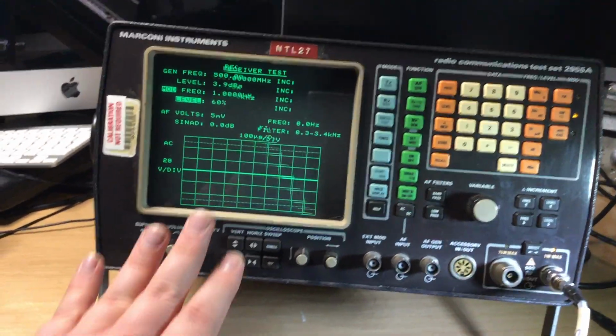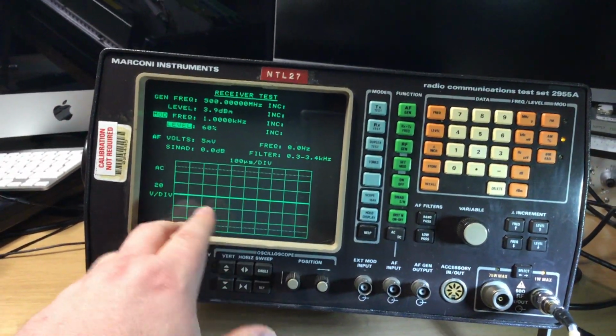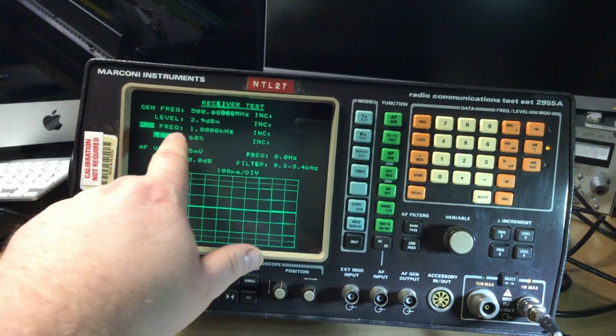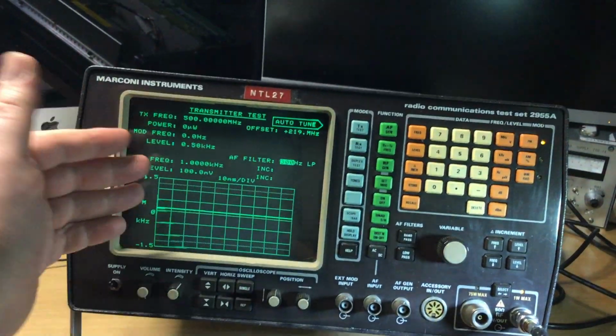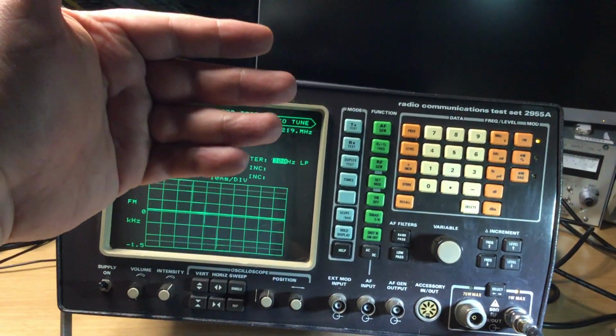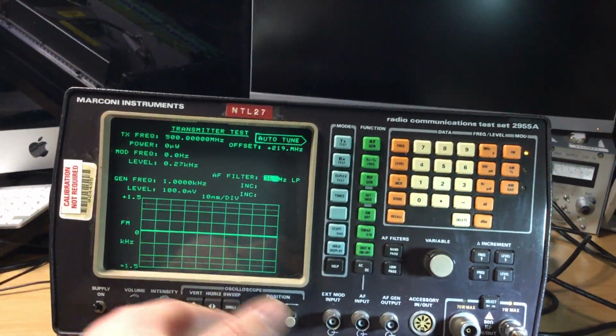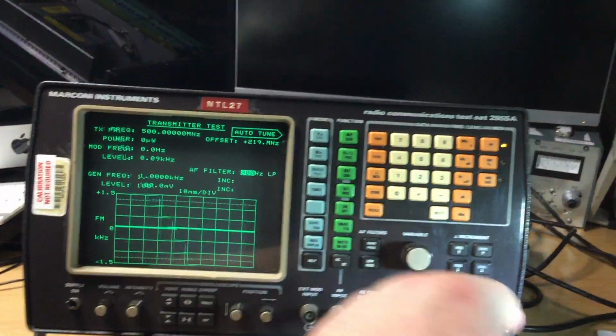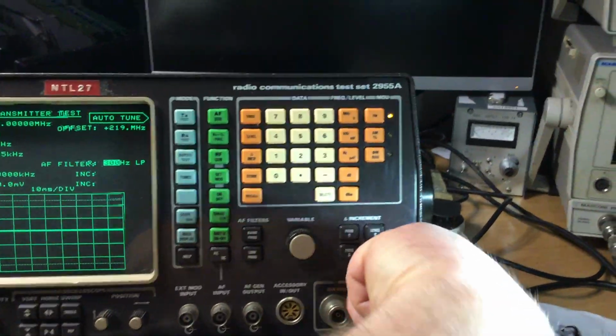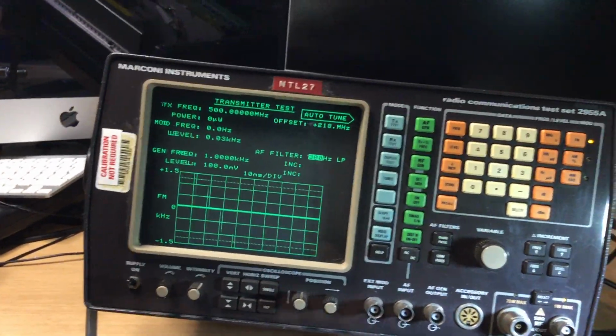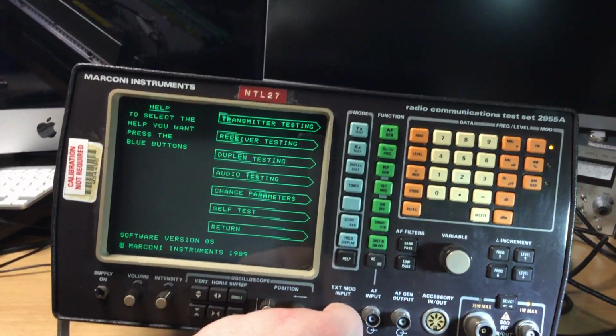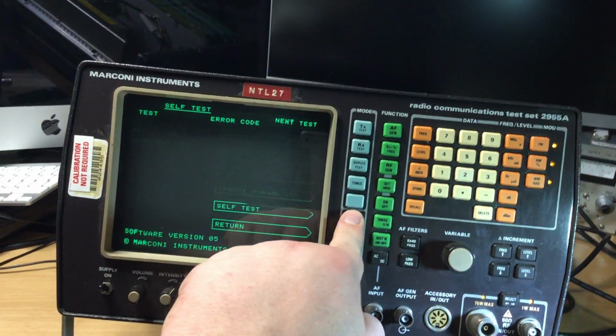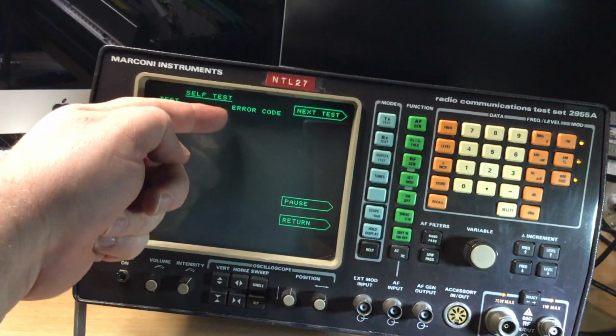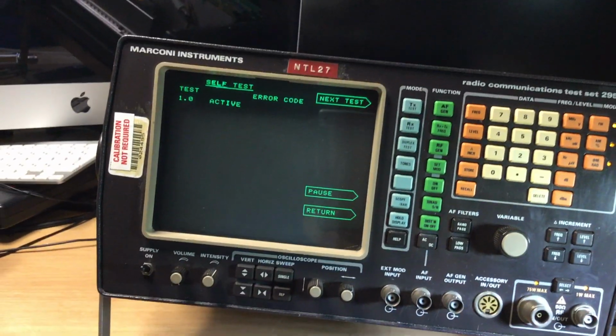I've got some 2955s that don't work. One of them has got no mod on the output when you're basically transmitting into the test set. For example, it doesn't read any modulation, so I'm going to do a video on that, which is a repair. Likewise, I've got a couple of them where when you do the self-test, they fail the tests as they're going down.